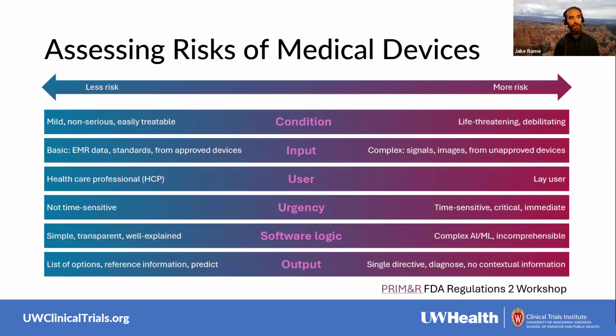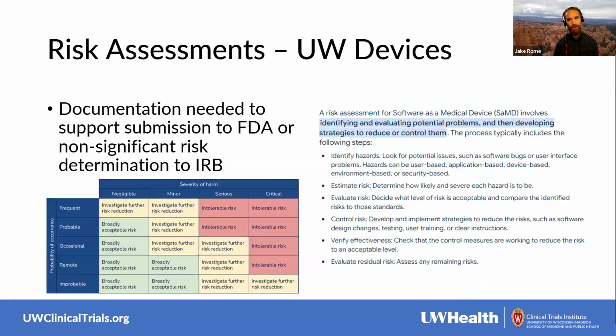I'm going to jump through this quickly, but I'll just note that medical device assessments are on a continuum. So you sort of have to look at what's less risky, what's more risky. That's extremely useful if you're developing your own devices to make sure that you're hitting all that you're trying to minimize the risk of the device so you can make that non-significant risk determination. And that's another thing that you want to consider as well.